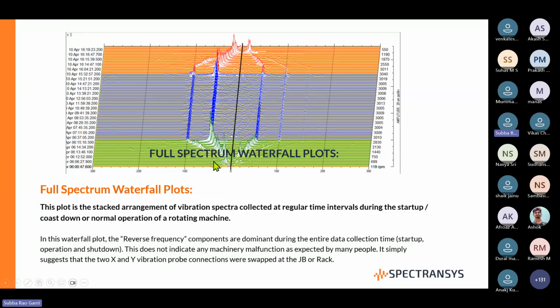This is a gimmick generated in the data when the X and Y probes are swapped. For example, the X probe from the field is connected to the Y probe on the 3500 rack, and the Y probe in the field is connected to the X probe on the 3500 rack. Then the data that you take, and the full spectrum generated from that, will come up like this one. When you see such activity, you can safely conclude that this is typically data generated by reversal of the probe connections.